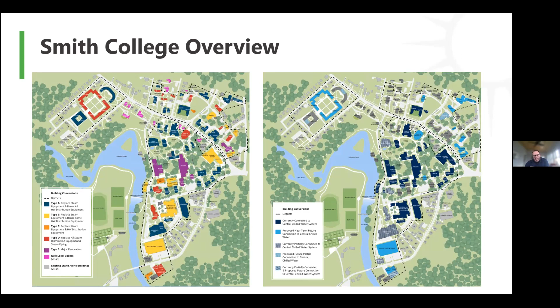They started to really consider their building stock, doing the same process we looked at for Ball State: understanding which buildings have which heating systems and which could operate at lower temperatures without major building-level modifications. They found a variety of systems could be set back effectively from 180 degree supply temperature down to 150 and even 140, eventually settling on 130 degree hot water supply for this campus, along with the need to add substantial cooling to existing buildings for comfort and to address deferred maintenance and other system upgrades.